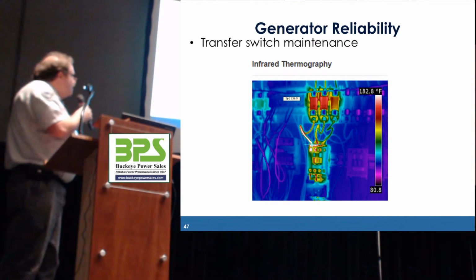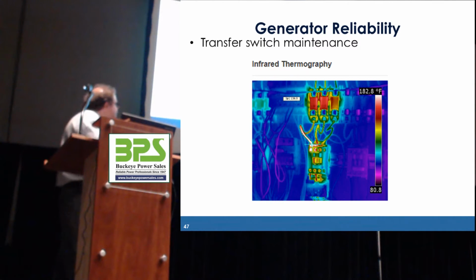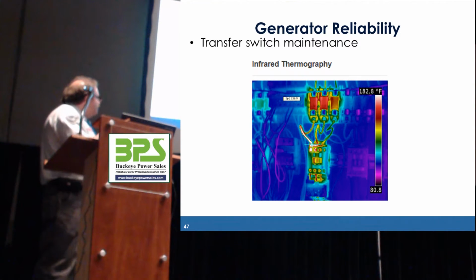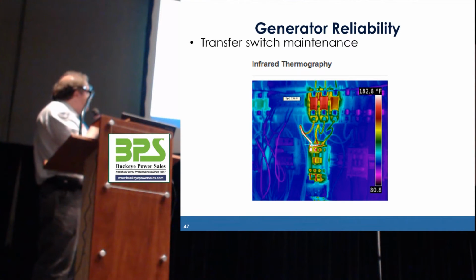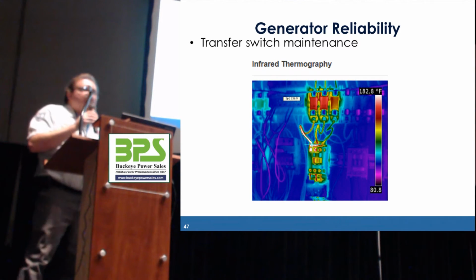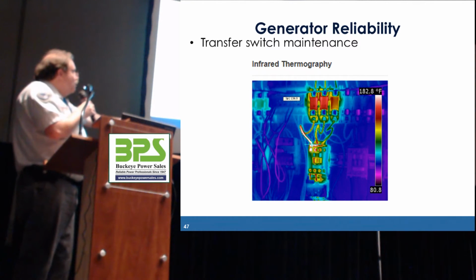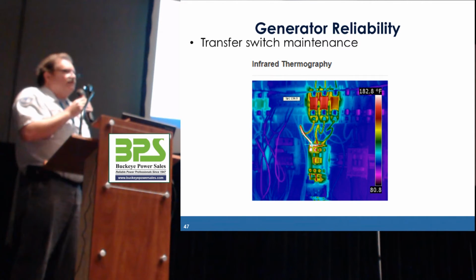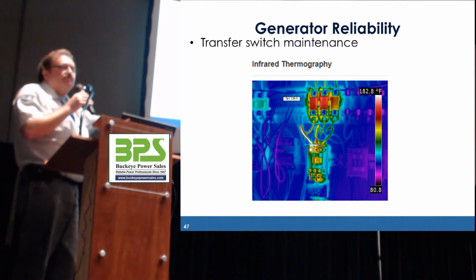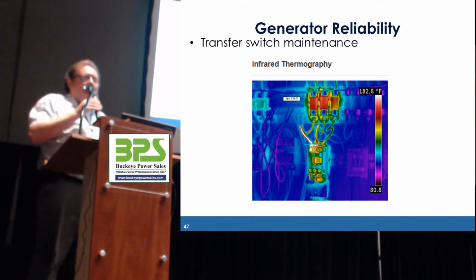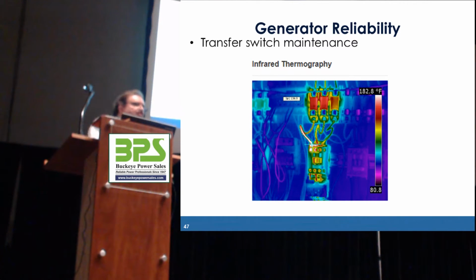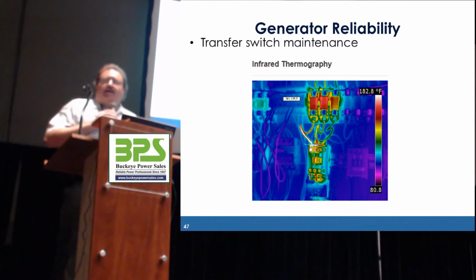So we can see here, this is a picture of a motor starter and some fuses up here. And look here, we have 3 wires. This connection point is showing white hot, and this wire is showing white hot compared to these other 2. So this picture right here shows us, wow, either we have a serious unbalance of the load right there, it's seriously overloaded, or more than likely that contact is loose. That wire is not making a good connection in there. Okay? So that thermal imaging should be part of your annual maintenance of not just the generator and transfer switch, but switch gear and the rest of your utility.